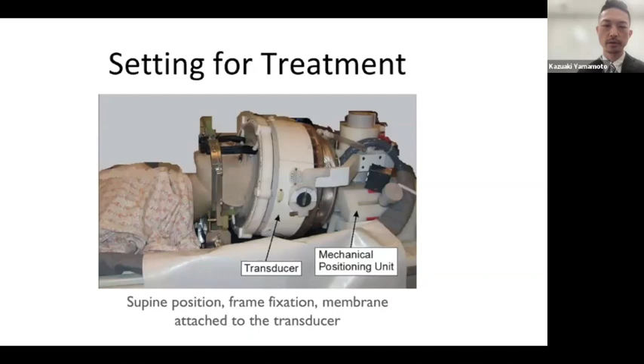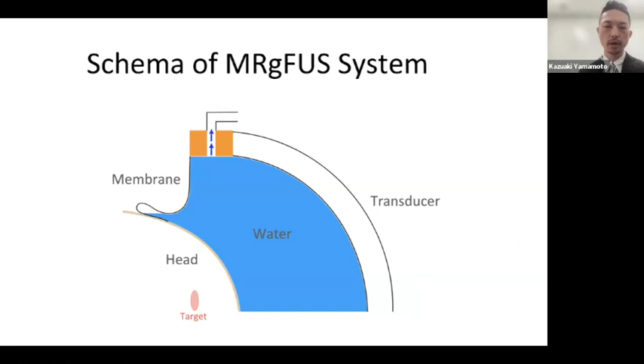Patient is placed in a supine position on an MRI table. The silicone membrane is attached to the transducer unit. This schematic shows the system. Water is filled between the silicone membrane and the transducer unit. It circulates in the system to cool the scalp and the skull to prevent heating. It's also degassed to avoid cavitation.